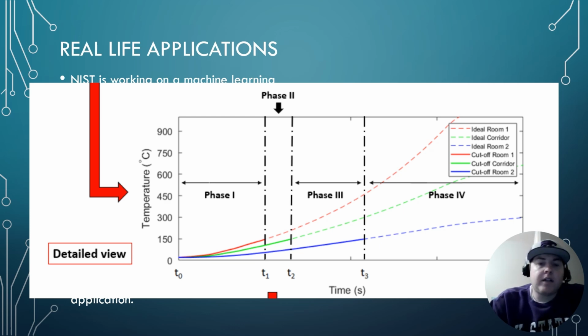After phase one, heat detector one is assumed to have been lost, so we're no longer obtaining data, but they're using the predictive performance of support vector regression during phase two to continue modeling data from that heat detector. And then you can see that heat detector 2 is still picking up data. After phase 2, heat detector 1 and heat detector 2 are both using predictive data, and heat detector 3 is the one that's still actually measuring temperature data.